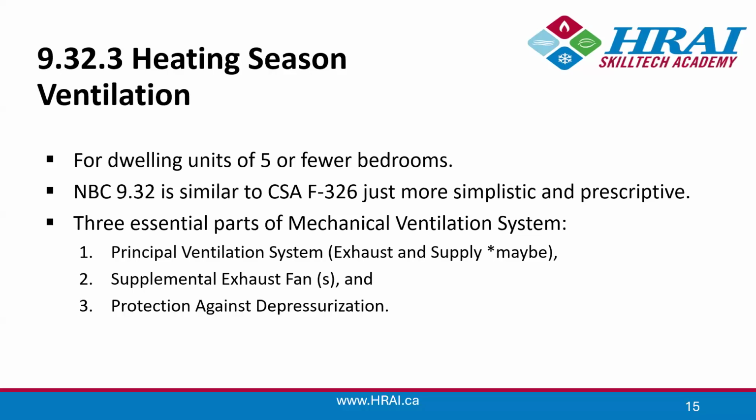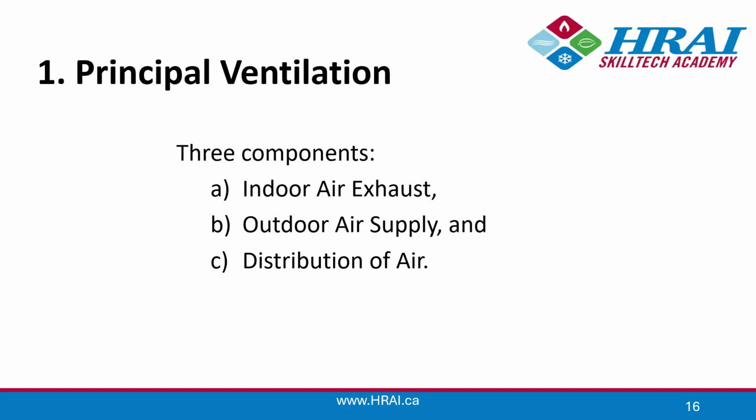There are 3 essential parts to a mechanical ventilation system. You have your principal ventilation system, and that's an exhaust and sometimes maybe a supply, supplemental exhaust fan or fans, and protection against depressurization. So if we take the first essential, the principal ventilation system, we'll look at that. And that has 3 components, including the indoor air exhaust, the outdoor air supply, and some kind of distribution of air. So when we start off with analyzing our principal ventilation, we have to figure out what sort of rate of ventilation we're looking for.